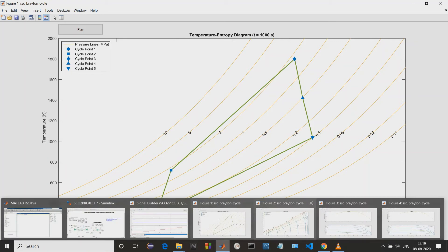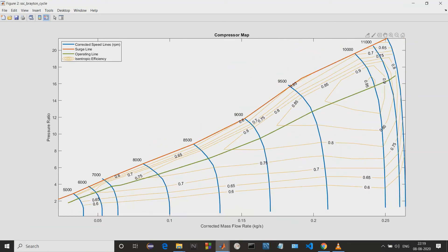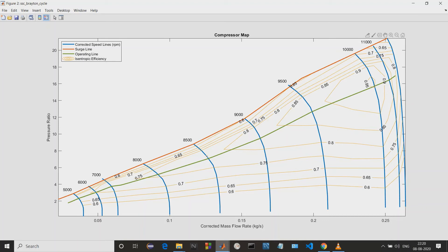Coming to the next, we have the compressor map. This red line shows the surge line — in this area, it may again cause damage to the compressors. To operate the compressor, we should always go with the values along the green lines, and we can get different isentropic efficiencies. Next we have the blue color line, which is known as the corrected speed lines.